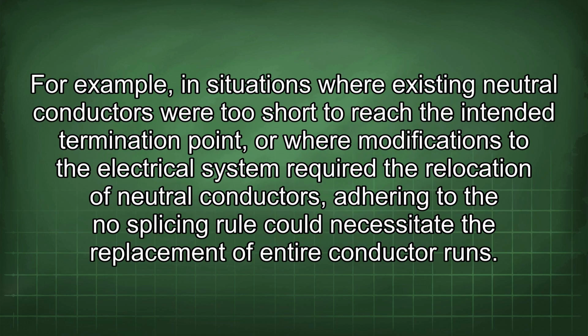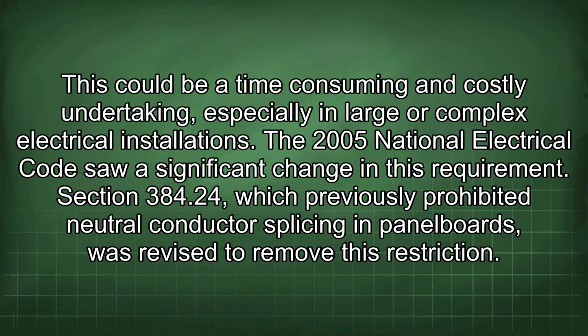For example, in situations where existing neutral conductors were too short to reach the intended termination point, or where modifications to the electrical system required the relocation of neutral conductors, adhering to the no-splicing rule could necessitate the replacement of entire conductor runs. This could be a time-consuming and costly undertaking, especially in large or complex electrical installations.